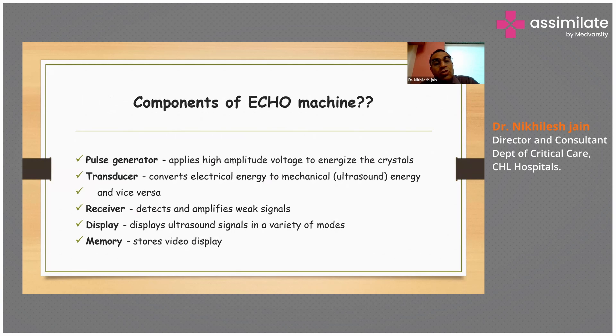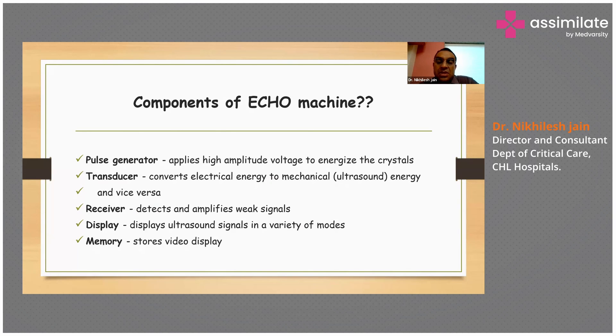What are the components of the echo machine? You've got a pulse generator, which applies high-amplitude voltage to energize the crystals. You've got a transducer, which converts electrical energy to mechanical energy and vice versa. You've got a receiver, which detects and amplifies the weak signals. Then you've got a display wherein you can see these ultrasound signals in a variety of modes. And you have a memory, which stores these displays in the form of a video.